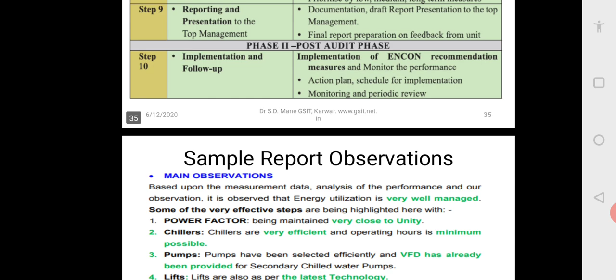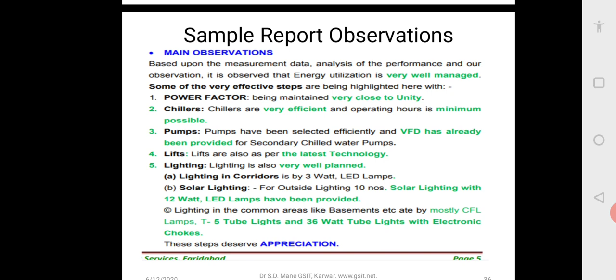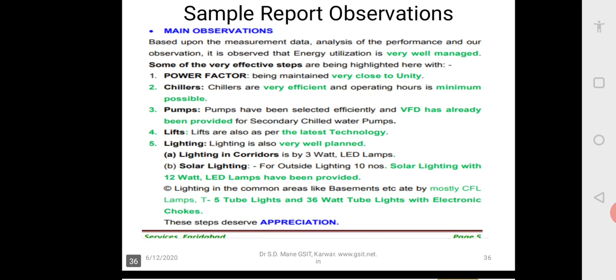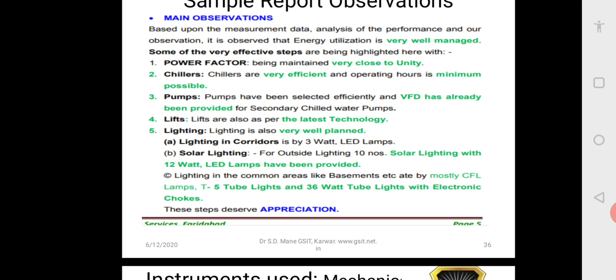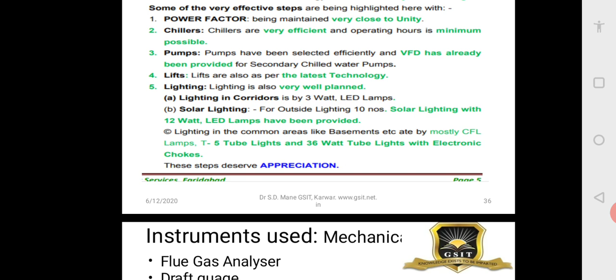So one report observation I just wanted to share. This is a new mall in Faridabad, audited recently. You can see a lot of awareness is there. The main salient points are the power factor, they are maintaining almost unity. That is very good. Then chillers are very efficient, pumps are high efficiency pumps, and VFD has been introduced. Lifts are also new technology. Lighting is good, LED lamps. Their only suggestion, what I saw, was that the old 36 watt tube lights with electronic chokes should be replaced with LED lights. So when all new technology is used, there is very little scope for further conservation.